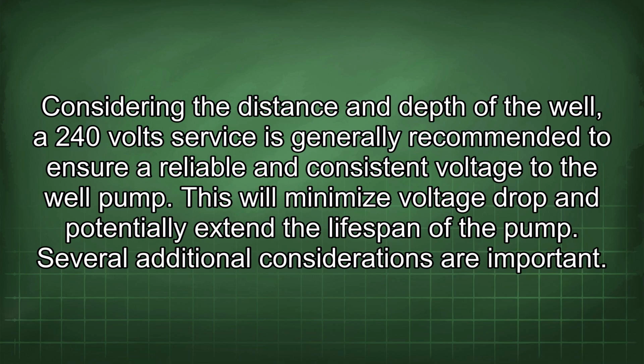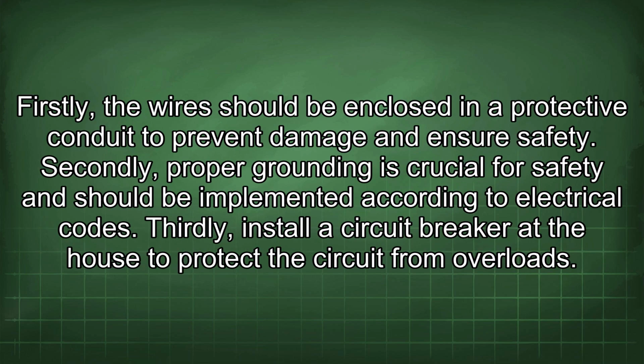Considering the distance and depth of the well, a 240 volts service is generally recommended to ensure a reliable and consistent voltage to the well pump. This will minimize voltage drop and potentially extend the lifespan of the pump. Several additional considerations are important. Firstly, the wires should be enclosed in a protective conduit to prevent damage and ensure safety. Secondly, proper grounding is crucial for safety and should be implemented according to electrical codes. Thirdly, install a circuit breaker at the house to protect the circuit from overloads.